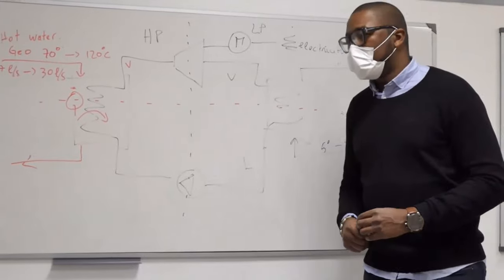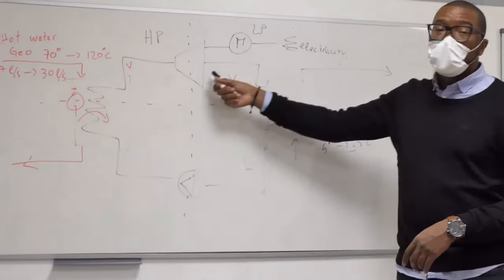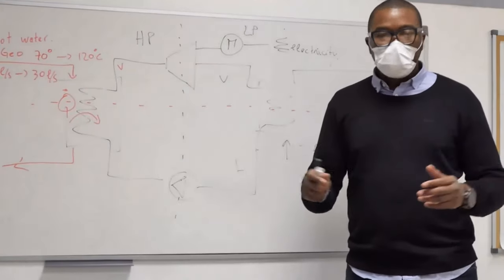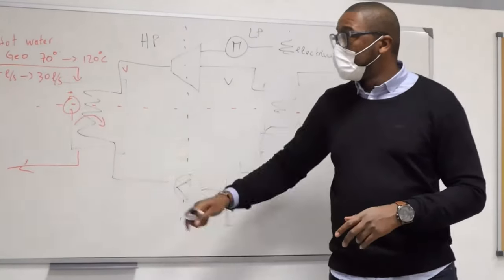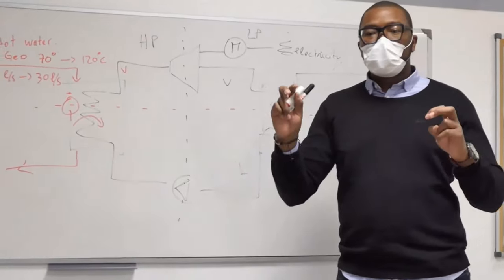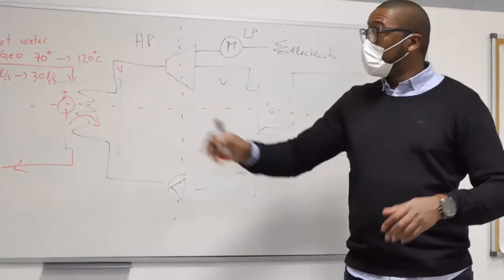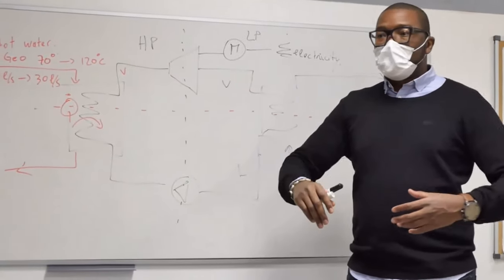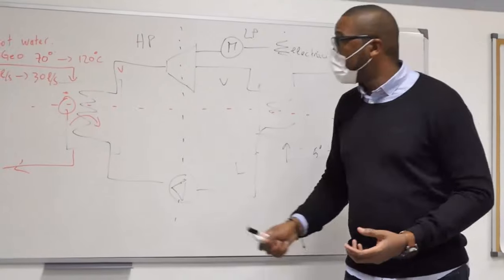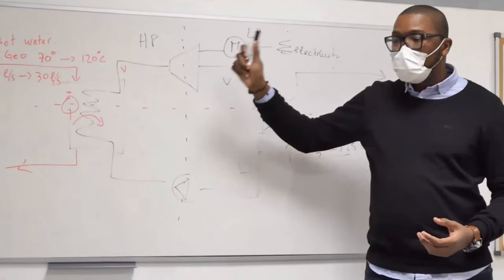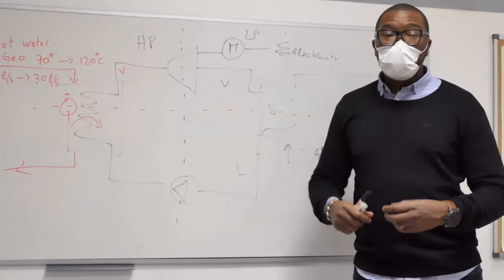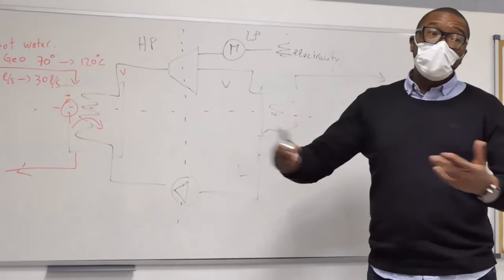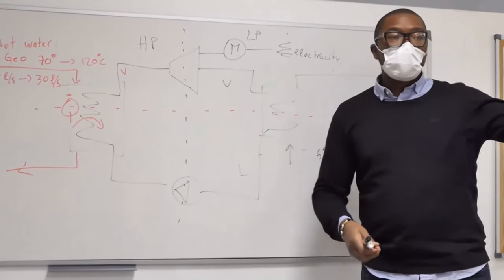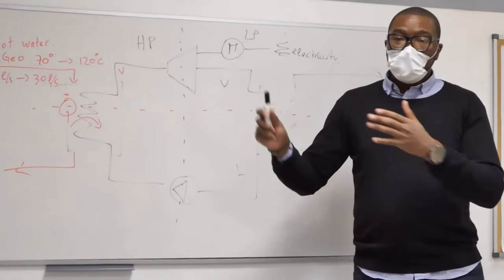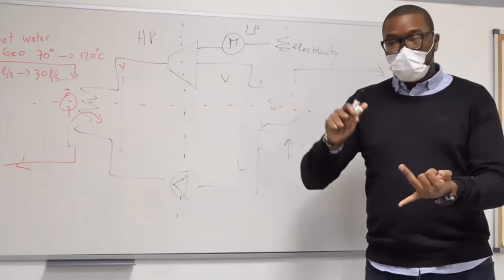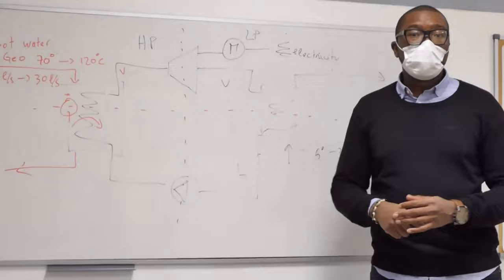Well, the difference is really focused on the turbine, because we design a turbine for a small range of thermal power and flow. But in the conventional geothermal power plant, we have higher temperature and higher power and bigger machines. We focus on this one. We develop a micro turbine with high speed, with really good efficiency. And the difference between the conventional ORC in geothermal and this one is the flow, the thermal power, and the efficiency at this low flow.